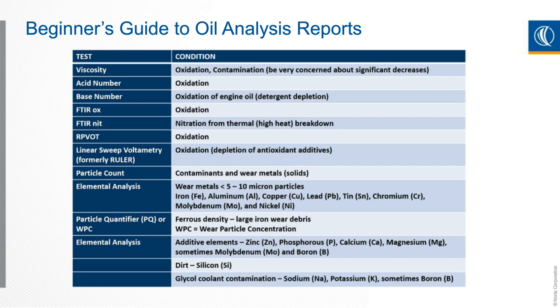Other elemental analysis would be additive elements or dirt levels or glycol contamination. All these things will be indicated in elemental analysis.